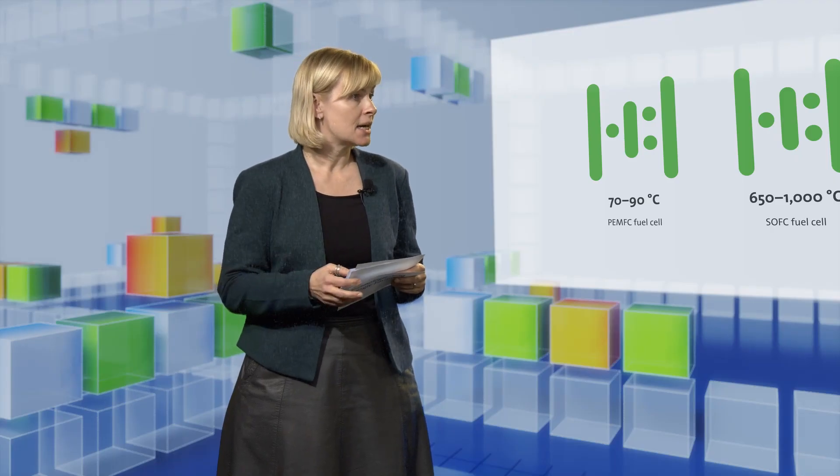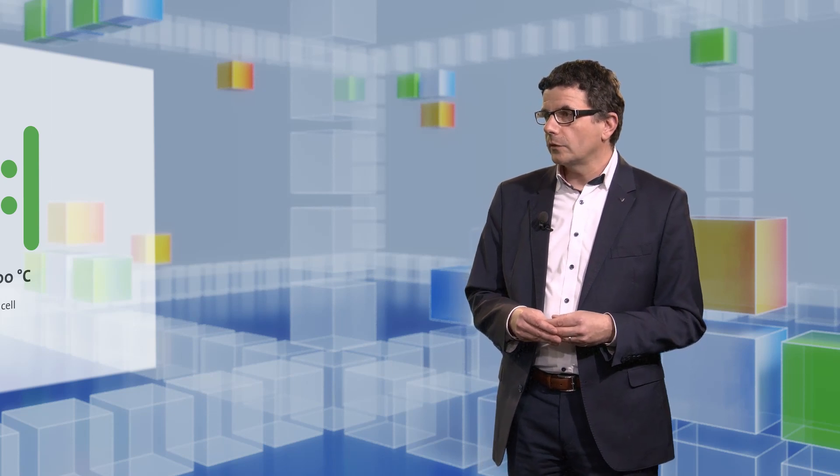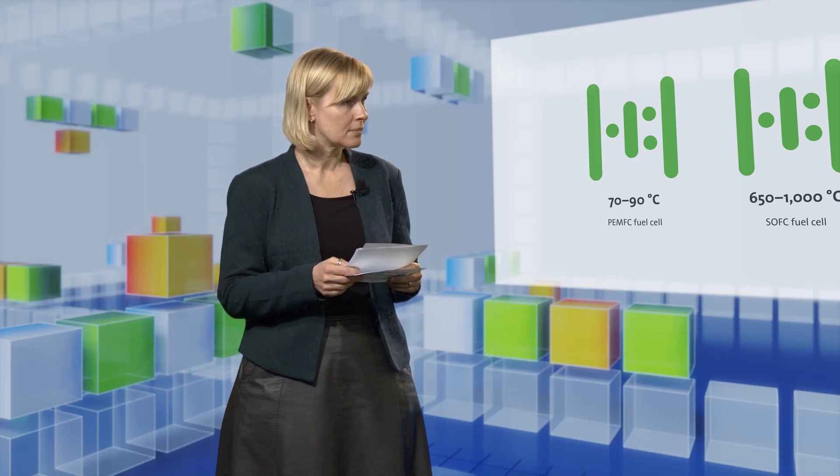There are different fuel cell heating system designs. In the heating market, we distinguish between two different technologies. They are the low temperature fuel cells, which are polymer fuel cells that are very widely used. There are already many thousands of devices in use. These work at temperatures around 80 degrees Celsius inside the unit, which is a relatively low temperature, hence the name low temperature fuel cells.